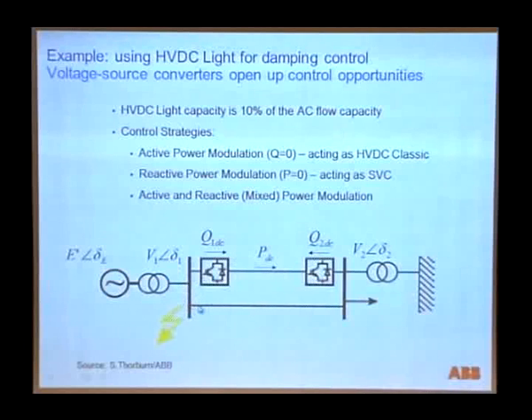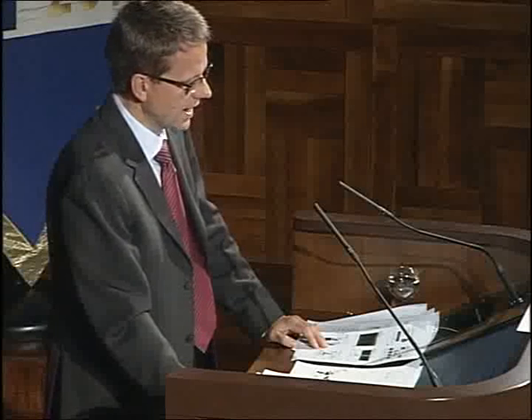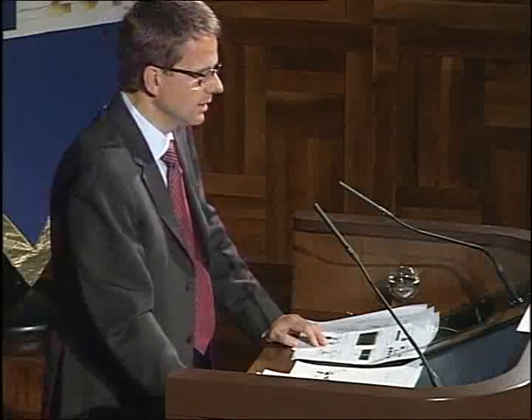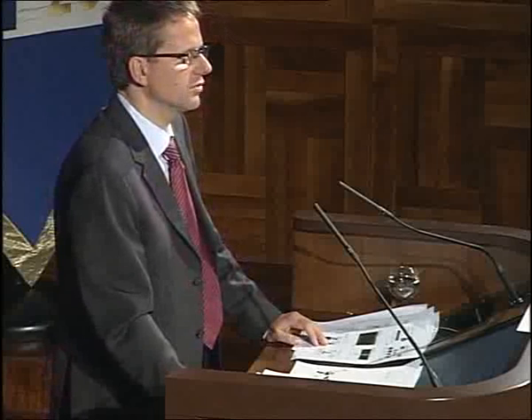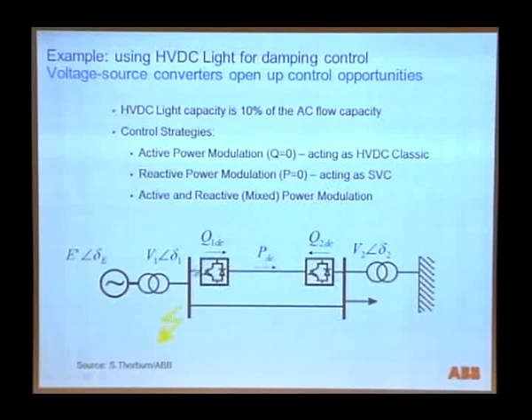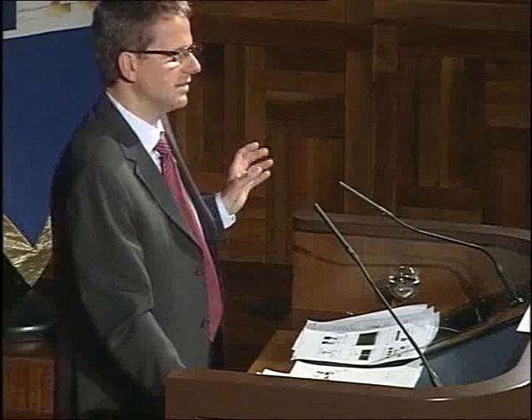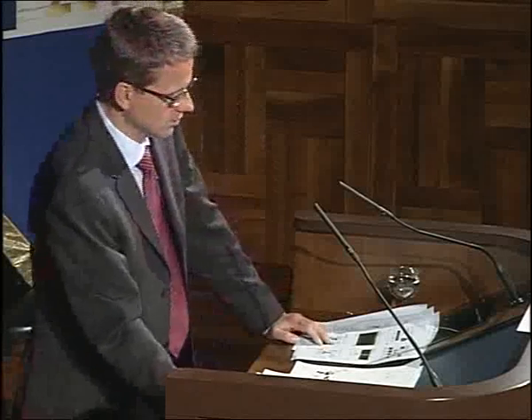Now, how do you deal with the control of disturbances here? Basically, 3 control strategies are shown here, and I want to emphasize these are not just control strategies in the sense that it's trivial to pick the best among them—these are 3 different control strategies played on a voltage source converter. If you pick an active power modulation, looking only at active power and ignoring reactive power, that gives you the conventional high voltage direct current control, what we call classic line-commutated converter control, which is much more limited.